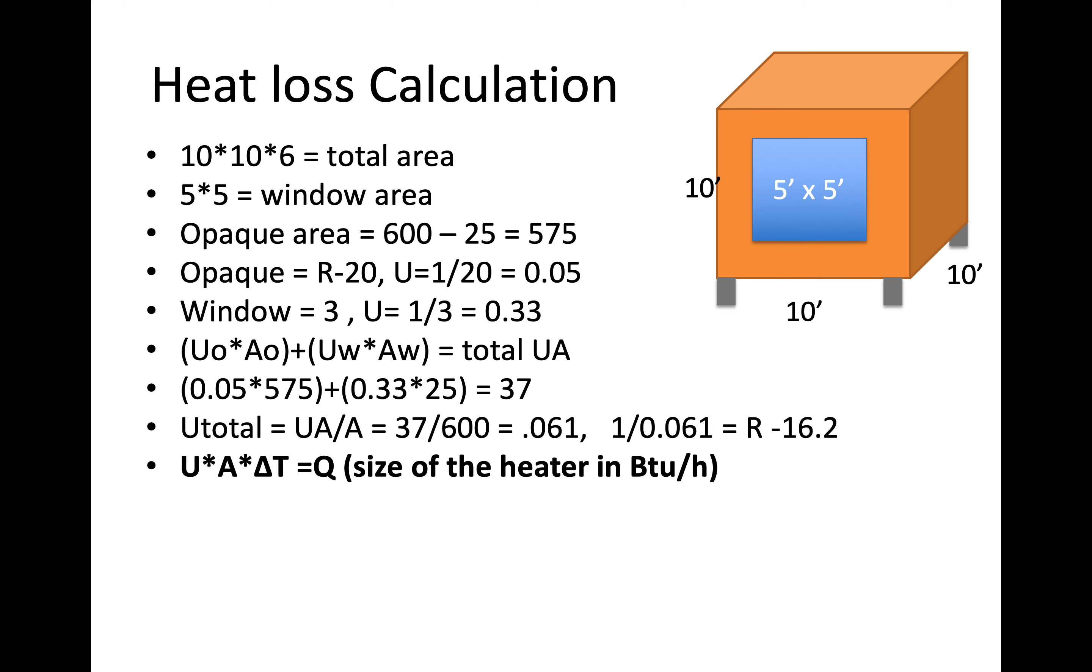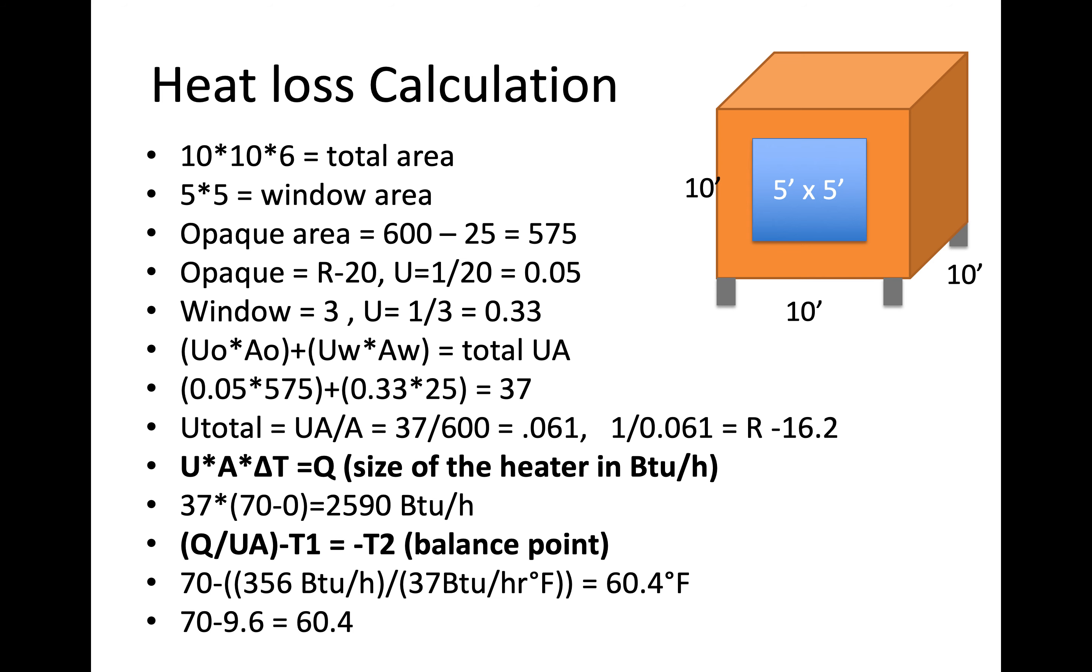But we want to calculate the size of the heater in BTUs per hour. So we can use this equation that we're going to visit a lot, which is u times a times delta t is going to be equal to q or the power of the heater. So in this case, we already have UA because we calculated it up in the original calculation. So we have 37 times delta t. In this case, we know that he's maintaining it at 70 degrees and that our design temperature is 0 degrees, which is convenient because then our delta t is 70. So if we multiply that through, we get 2,590 BTUs per hour. So that's the size of the heater that we would require just to keep the space warm.